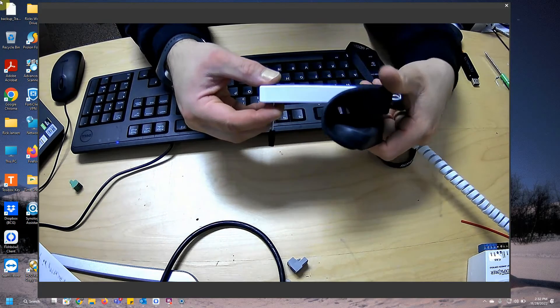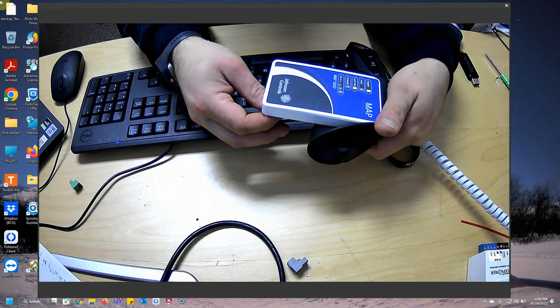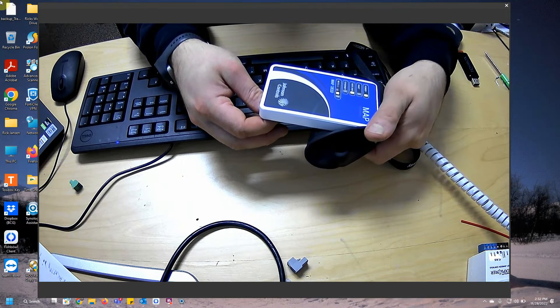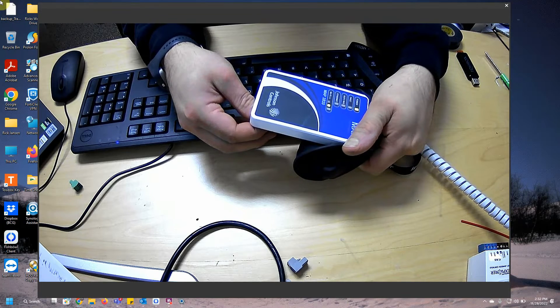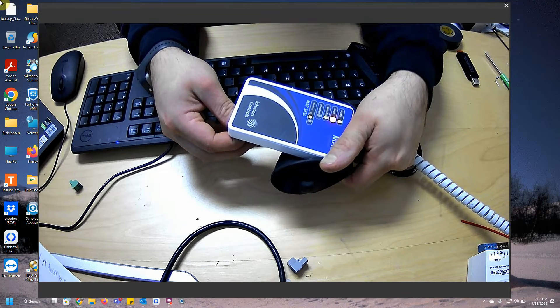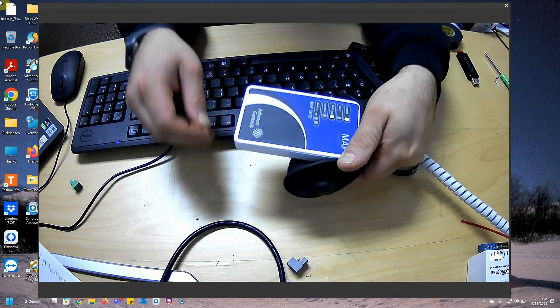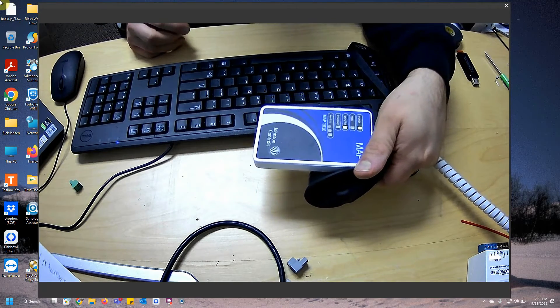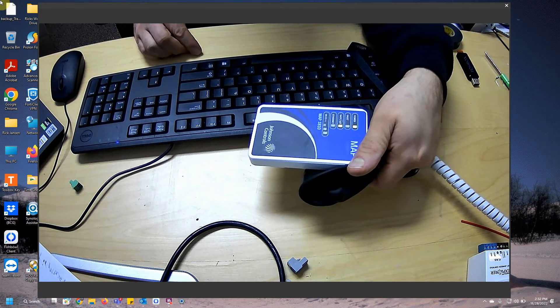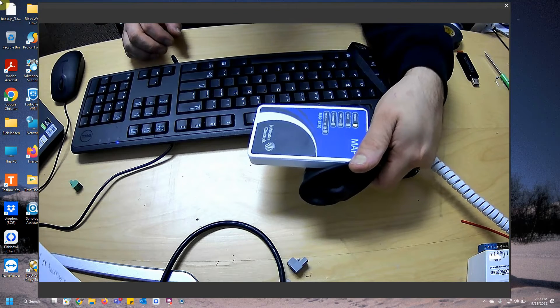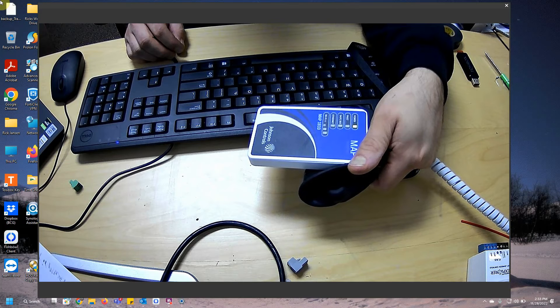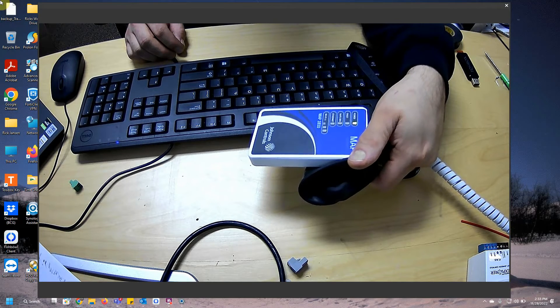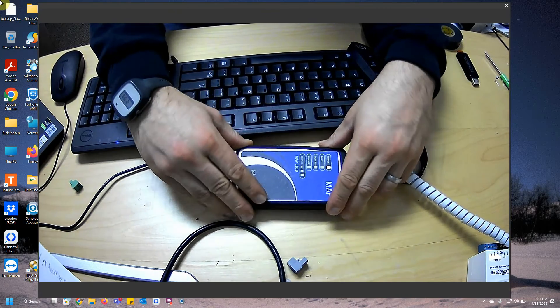Now I'm going to flip this back over because we're going to watch for this fault light. We're going to push and hold this down for six seconds. What we're waiting for is that fault light. So it flashes slow like that, and we're going to wait for it to flash fast. Let off the button and push it down one more time. It doesn't look like it's doing anything right now, but the factory reset process has actually begun. Now this is going to take a couple minutes, and in the meantime, we can just go ahead and set this back down and let it do its thing.